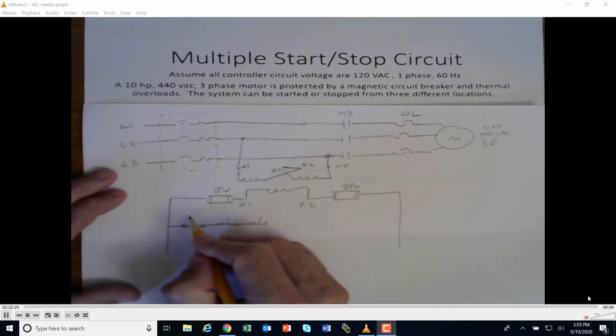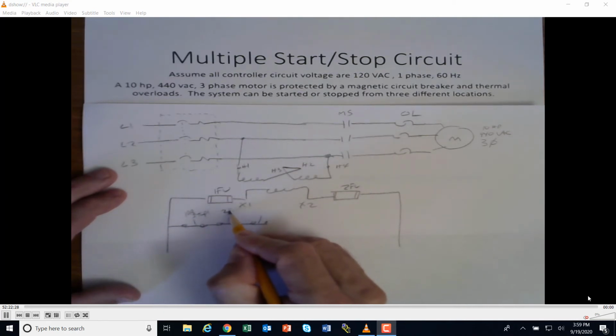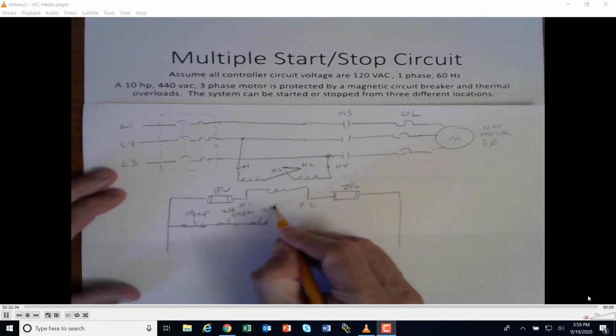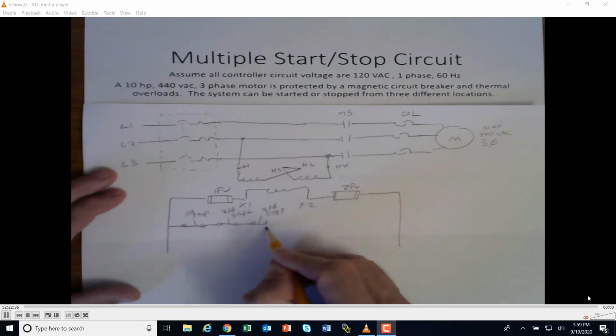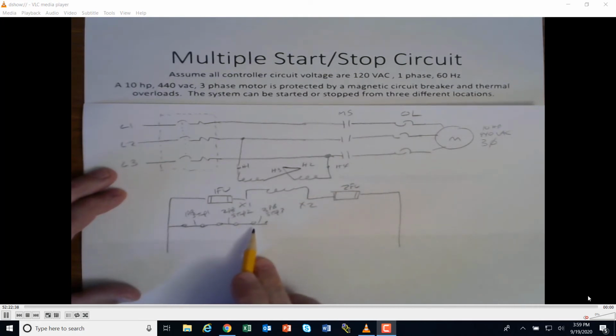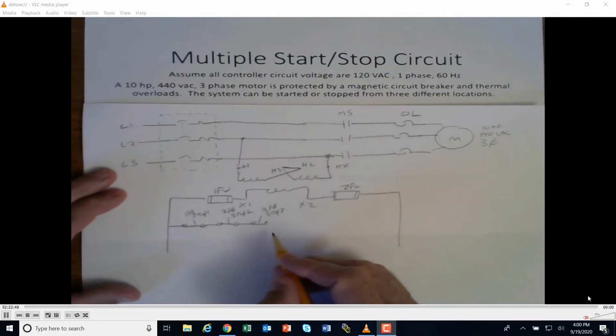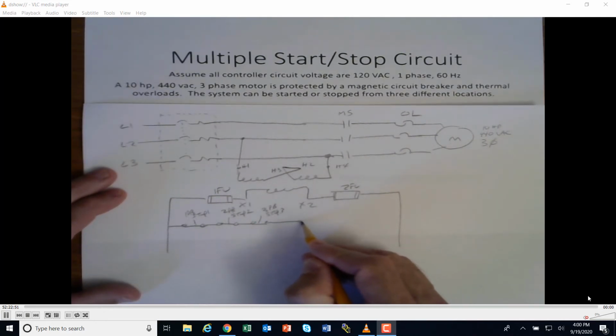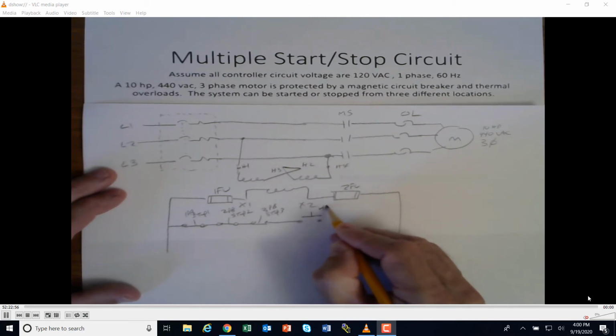This would be 1 PB, stop 1; 2 PB, stop 2; 3 PB, stop 3. So we've got 3 normally closed push buttons - pushing any of these opens up that circuit. Now we want it started from 3 different locations. So if I came here, I'd have a start, 4 PB, which would be start 1.